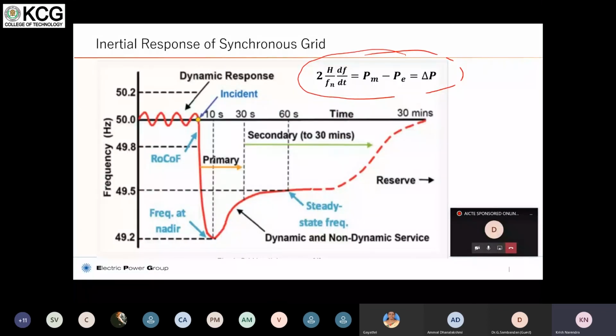This happens because if you lose a lot of electrical load, then the generators, which are synchronously connected, try to speed up, and therefore the frequency goes up. When generation goes off in a synchronous grid and the load remains the same, in order to supply the load with lesser generation, the speed of the generators will come down and hence the frequency drops.